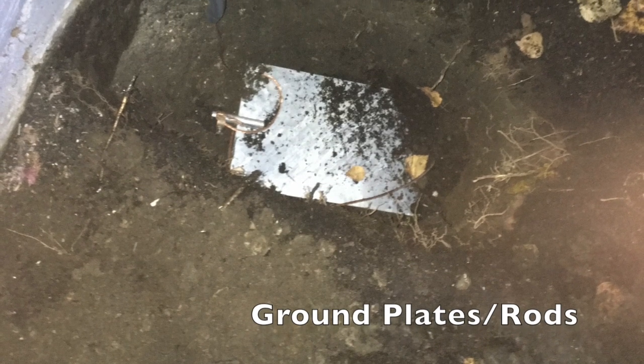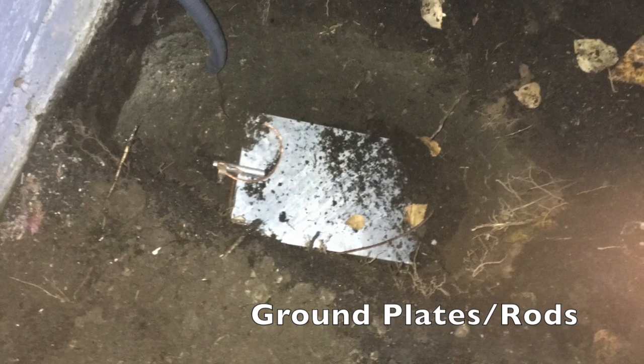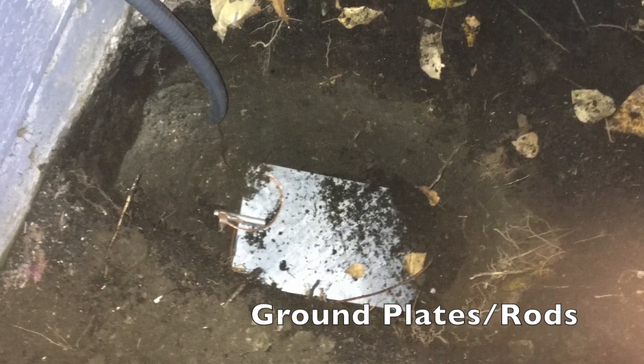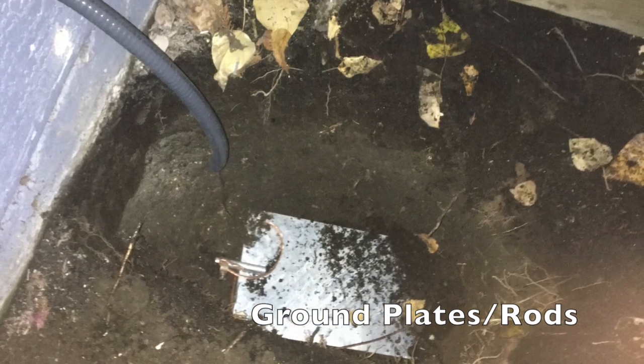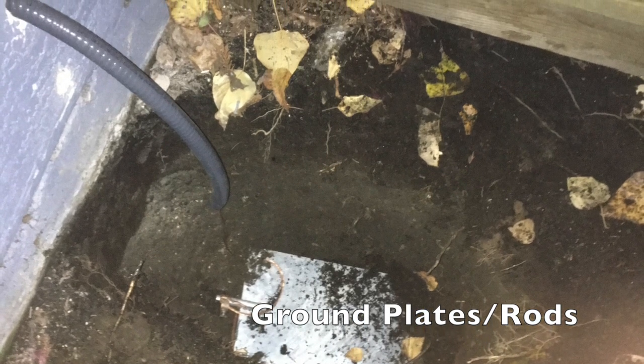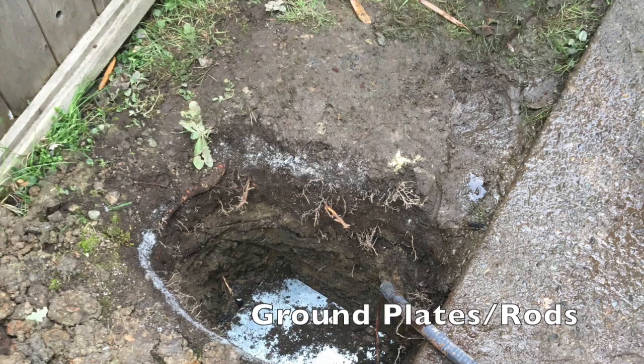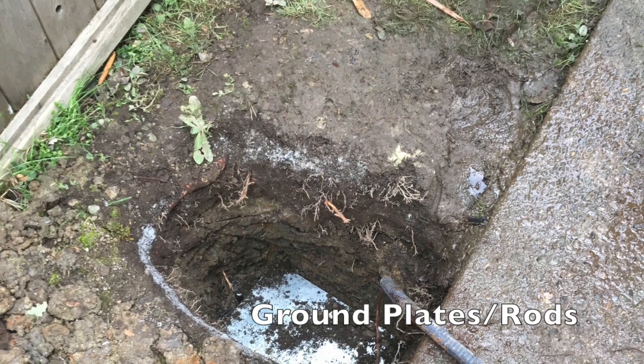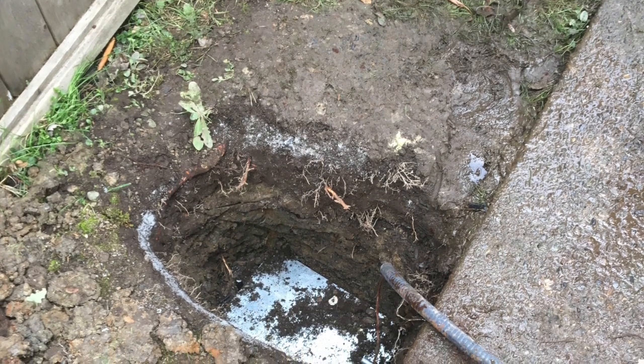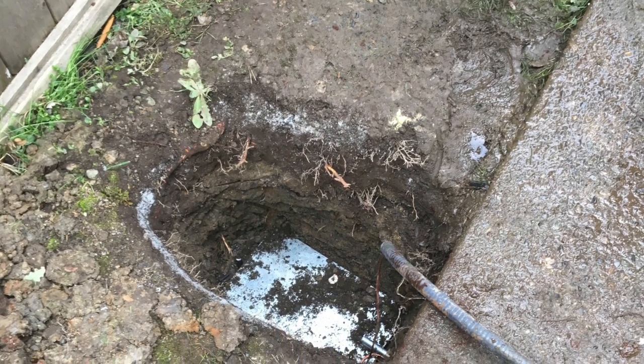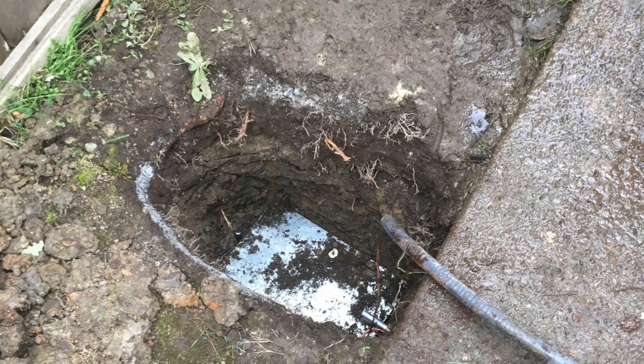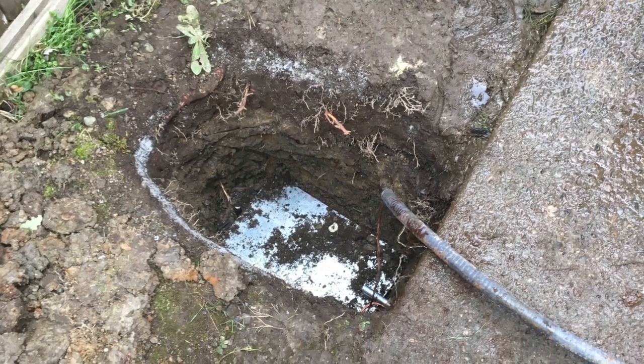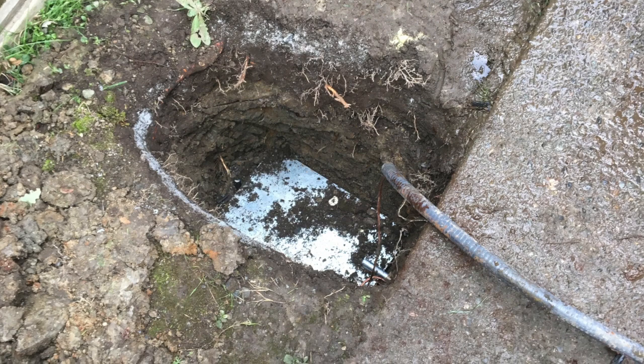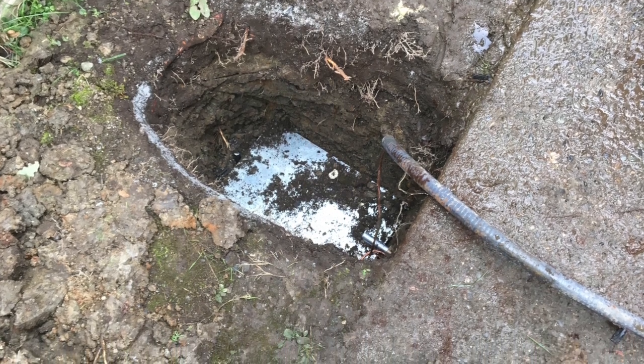Along with upgrading your power to 200 amp service at your home, we also need to update your grounding and bonding in your home. So in this picture, as you can see, there's a grounding plate that has been dug 2 feet into the earth. In some cases, the ground plate is not accessible directly from the back side of the electrical panel. In this scenario, as you can see in the image, there was a sidewalk that restricted our access into the dirt right from the back of the panel.